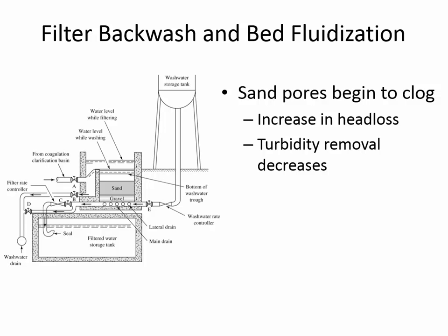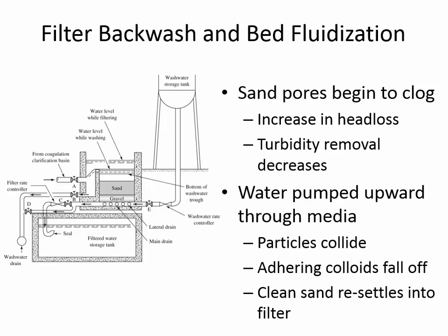And this is just talking a little bit more about the backwash phase and why we do it. The purpose of the backwash is to increase the void sizes again once it gets clogged with all of the particles. It's just the process of taking a pressurized water source. It doesn't have to be from an elevated tank. We could use pumps. But this is just illustrating that the water is at a higher pressure and so the velocity going up of the water during the scour phase is much faster than the usual flow rate that's going down. The loading rate that we'd usually apply to the sand filter is a much slower process.